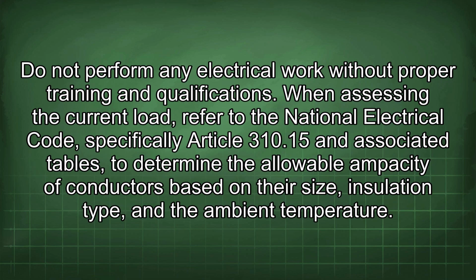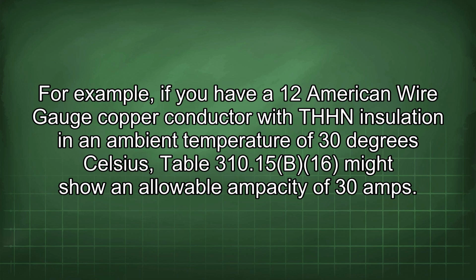Do not perform any electrical work without proper training and qualifications. When assessing the current load, refer to the National Electrical Code, specifically Article 310.15 and associated tables, to determine the allowable ampacity of conductors based on their size, insulation type, and the ambient temperature. For example, if you have a 12 American wire gauge copper conductor with THHN insulation in an ambient temperature of 30 degrees Celsius, Table 310.15(B)(16) might show an allowable ampacity of 30 amps.